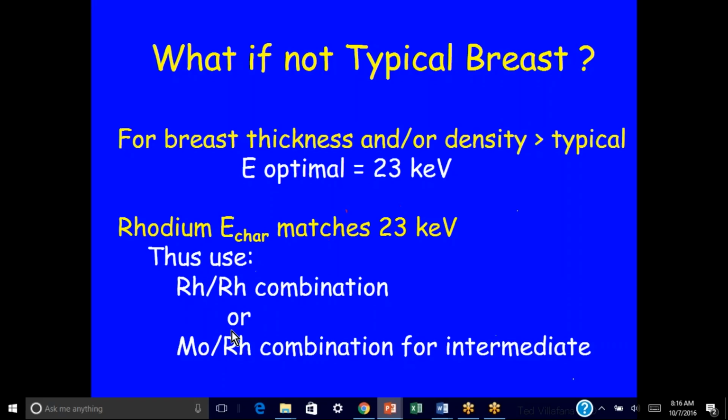Now, not all mammo machines have the facility of providing both molybdenum and rhodium. There are only a few vendors that have that combination available. But the way those would work would be the following. You have a filter wheel. One half of the filter is molybdenum, one half is rhodium. You have a target with two targets for each size: a large and small molybdenum target, and a large and small rhodium target. You have to have a target material that has separate tracks, one for molybdenum and one for rhodium. And the way it actually works is as follows.